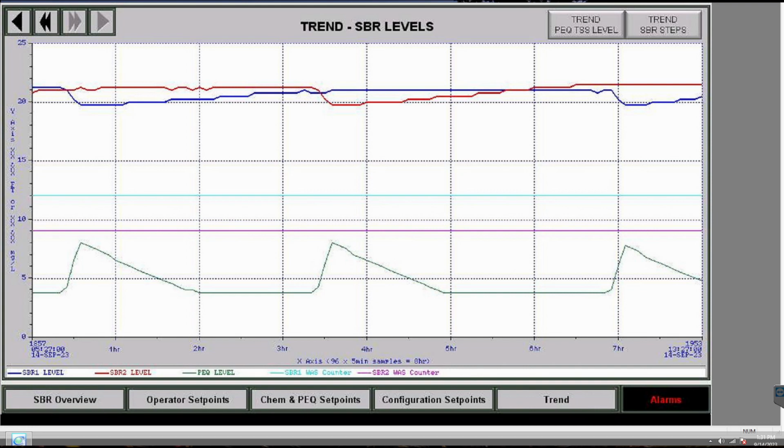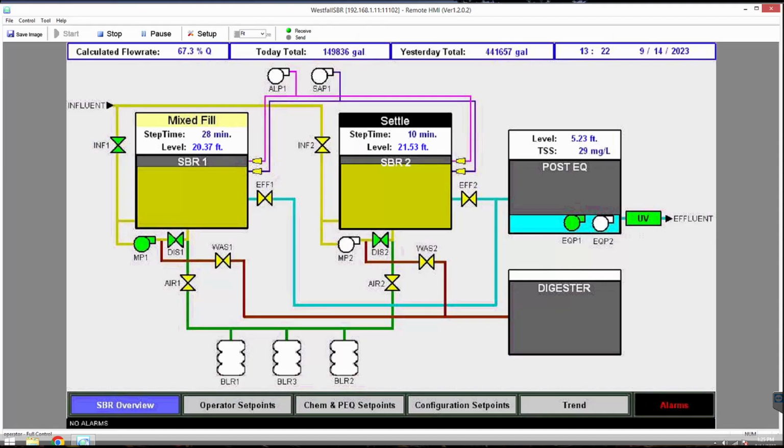But you've got to think of flow proportional software or SBR logic software like a continuously variable transmission, if you're following my example here. Completely following your example. Right? Yep. So it's not like you're in one mode, normal mode or storm mode. It's constantly calculating. If anything, there's like 300 different modes that it could be in. Am I at 2% of design or 20% of design or 57% of design or 130% of design? It's continuously going to be adjusting treatment steps and the length of each treatment step based on that percent of design.